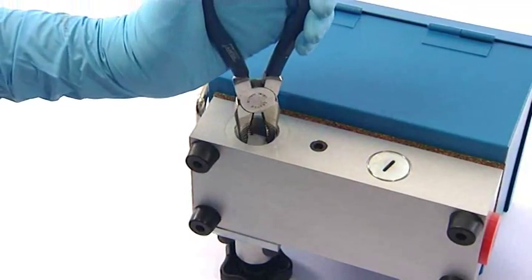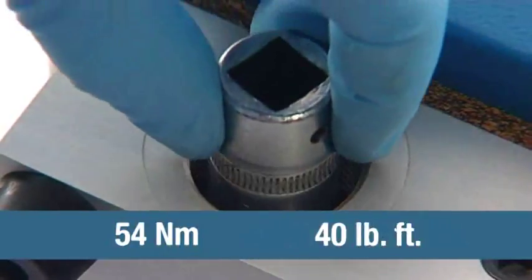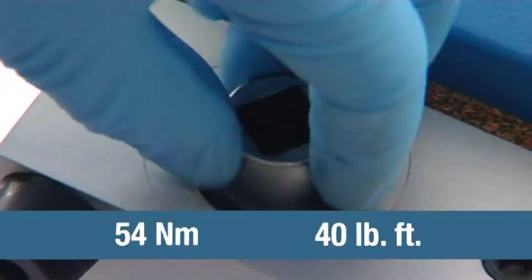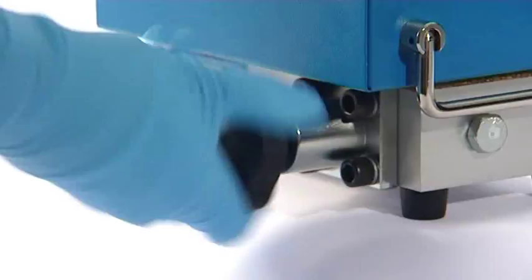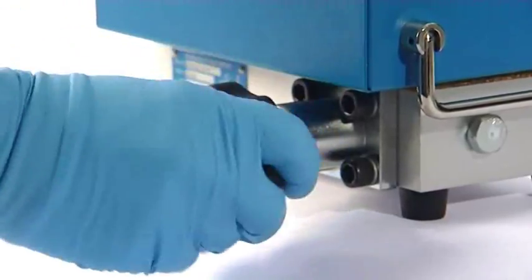Then screw in the disk holder and tighten to 54 newton meters or 40 pounds foot. Finally, unscrew the load valve fully and your tester is ready to use.